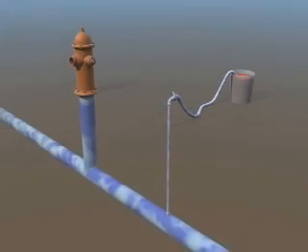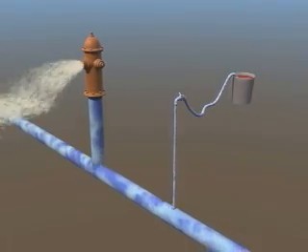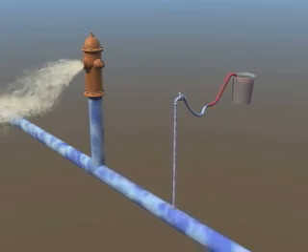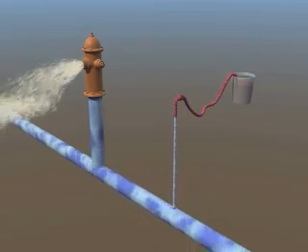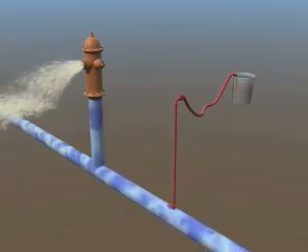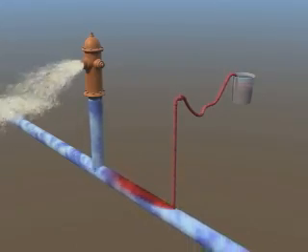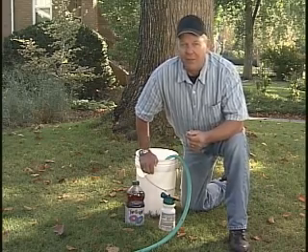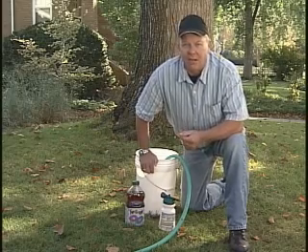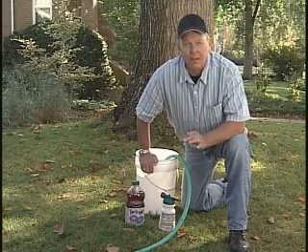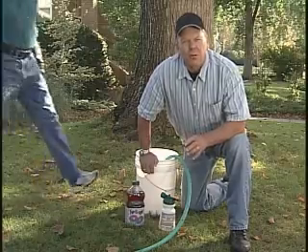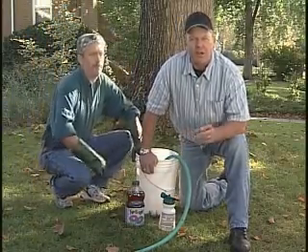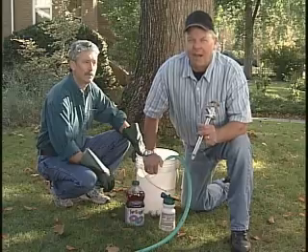This could easily pull the contents of this bucket into the water system. The backflow created by the open fire hydrant pulls the water backwards, sucking the fertilizer back into the hose and eventually into the water distribution system. So, the backflow created in the water system by the firefighting and the cross-connection between the hose and the bucket contaminates the water system. But you can prevent this problem with a solid cross-connection control program. A simple backflow prevention device like this one installed on the spigot at the house prevented this water from going backwards at the spigot.